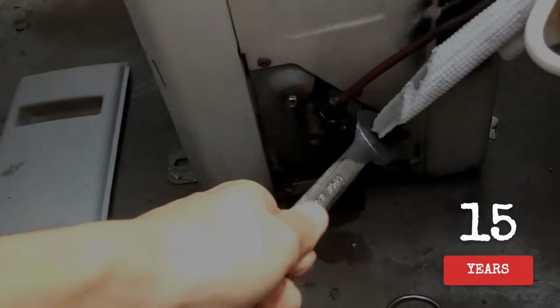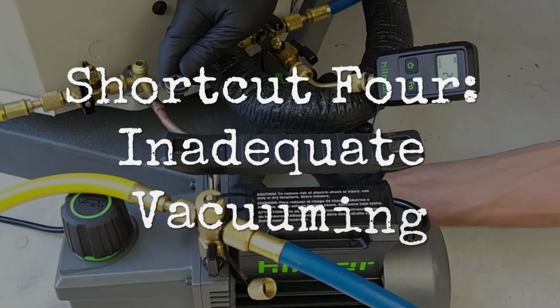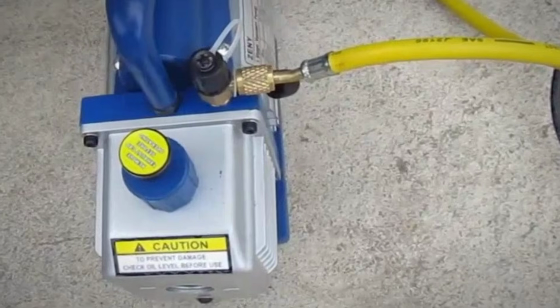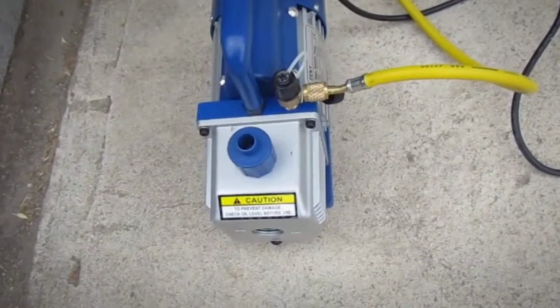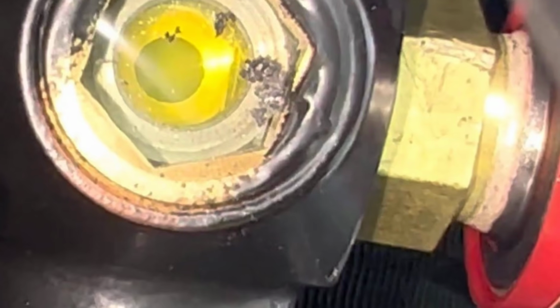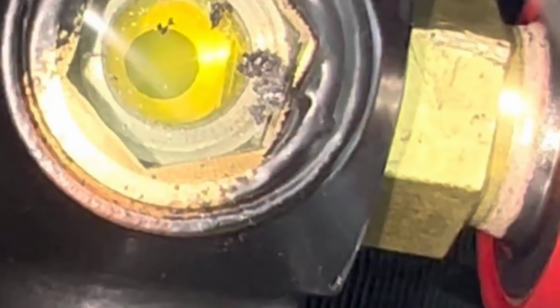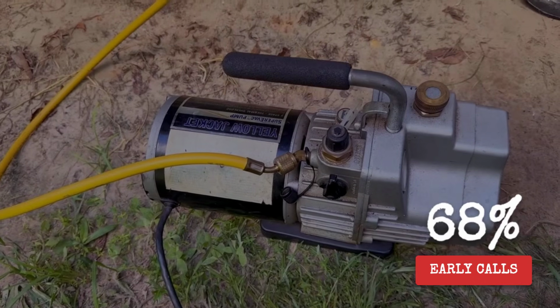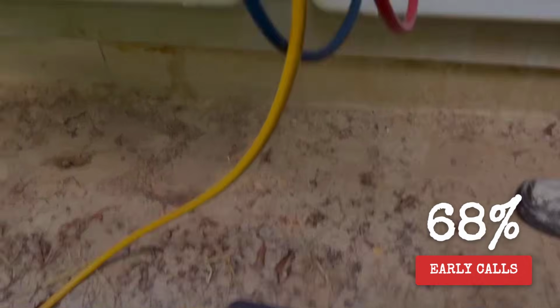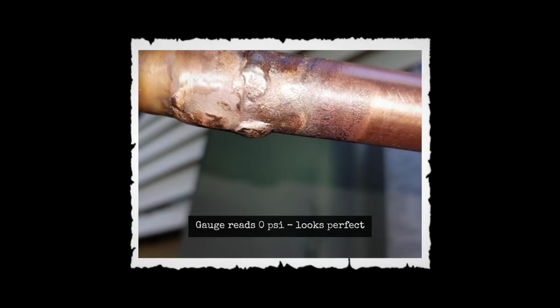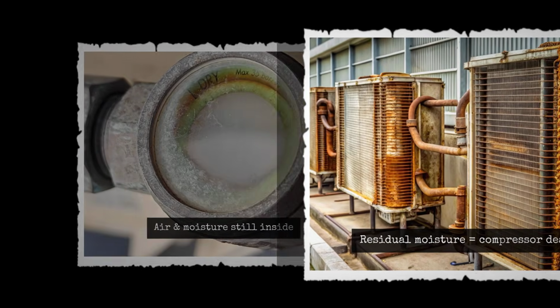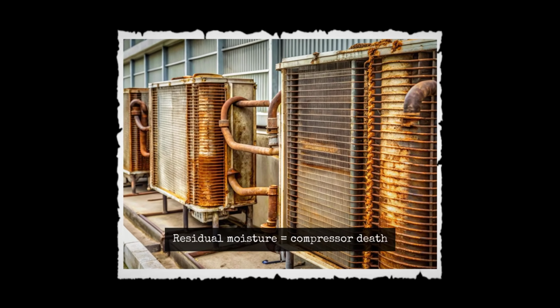Shortcut 4. Not vacuuming the system properly. Before refrigerant is added, the system should be evacuated with a vacuum pump to remove all air and moisture from the circuit. A proper evacuation takes time. The shortcut is a partial vacuum that looks fine on a gauge and that hides contamination, which destroys the system from within over the following years.